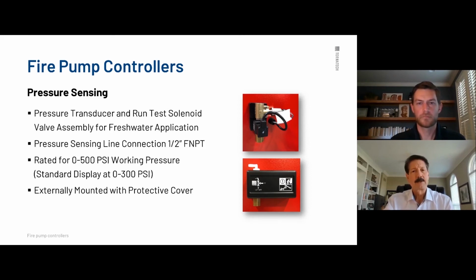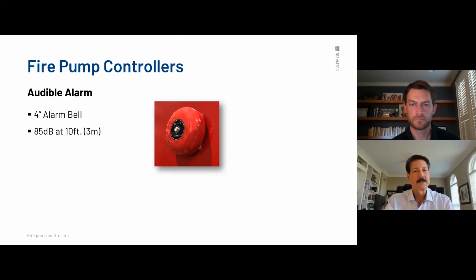Again, not to reiterate, but we have the same pressure block. We have a pressure transducer. We have a manual test solenoid here. The 0 to 500 psi is working pressure, standard 0 to 300, externally mounted wetted parts. It's the same as the electric. So I will work through this because it's redundant.